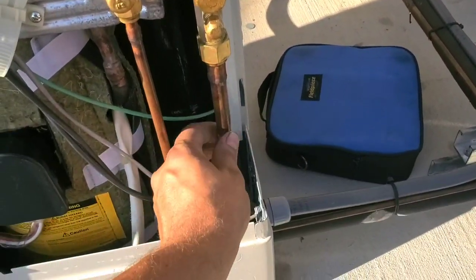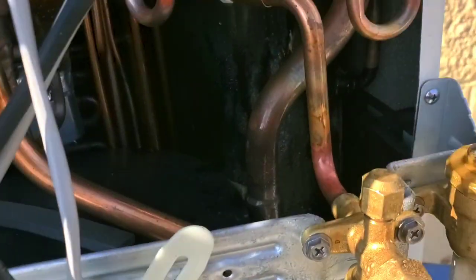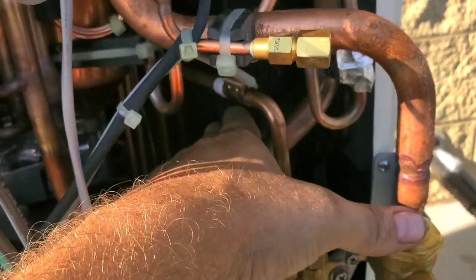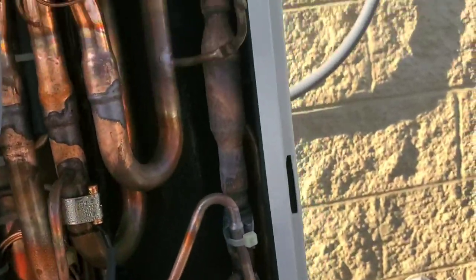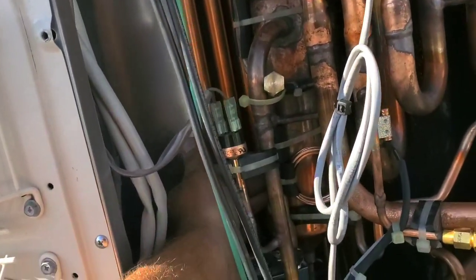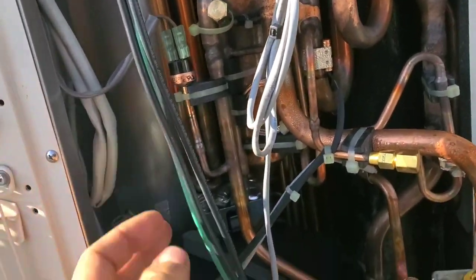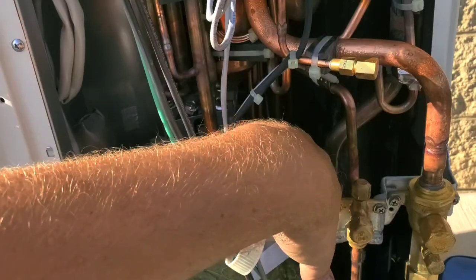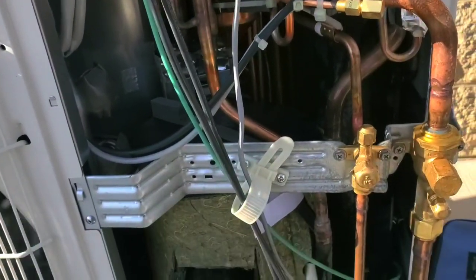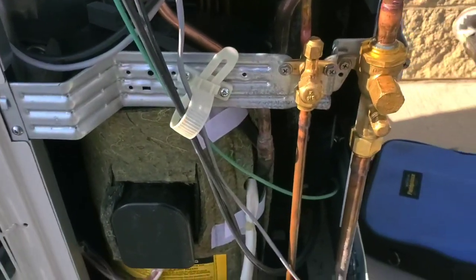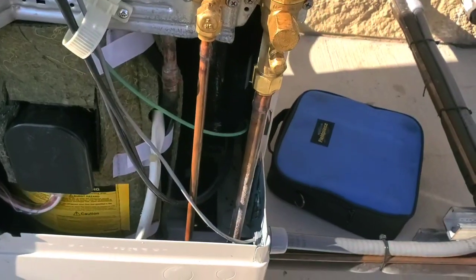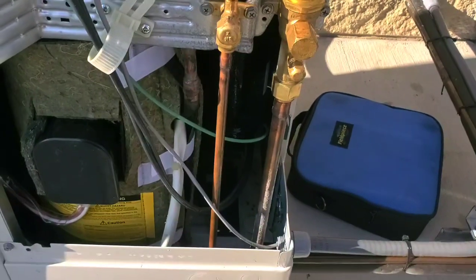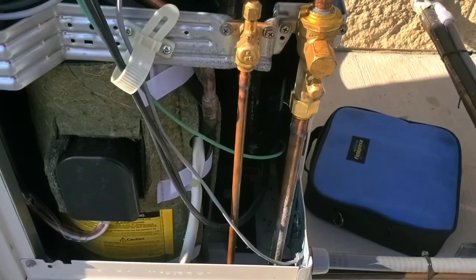There's ice on the suction line here. There's ice on the receiver right there. There's ice almost up to the compressor. Heat exchangers are cold, except the one on the left. The discharge line's nice and hot. So everything's good. It's just a mini split, so it's garbage. But other than that, we're straight. Never mind the routing of the wires that are slightly inconvenient.